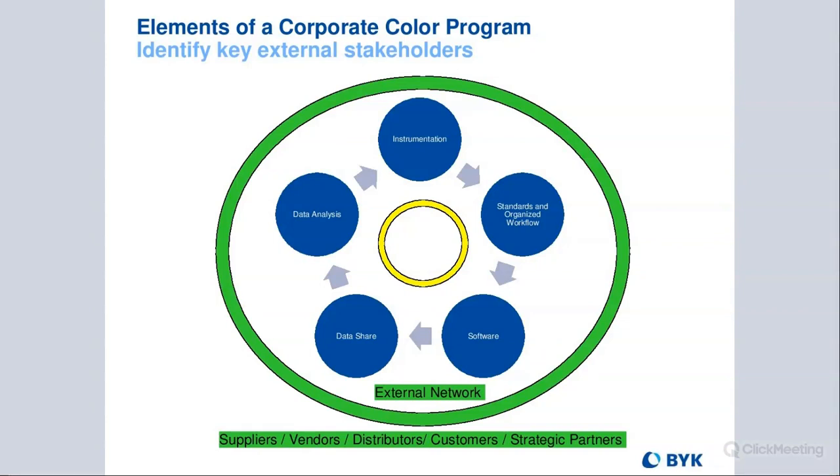And the processes and procedures have to be the same. Like I mentioned several times, for the BYK-mac, because it's multi-directional, direct illumination, if you don't always measure the same way, you're going to have different results. At one of the OEMs, they kept telling me something's going on with second shift. The data is always different. We realized it was how they were holding the instrument when they measured. Just that simple thing caused a huge problem where they thought there was an issue with second shift. Yep, so these are significant things. Consistency is the key.